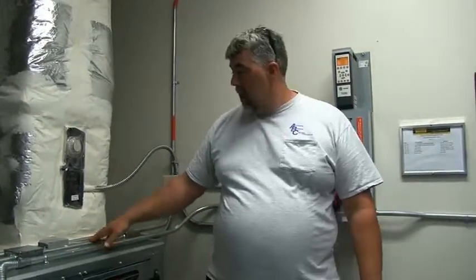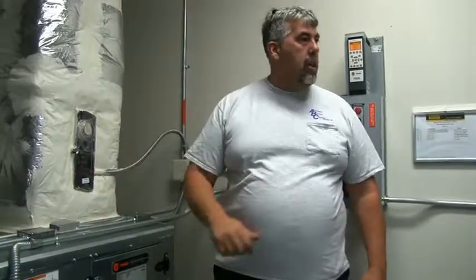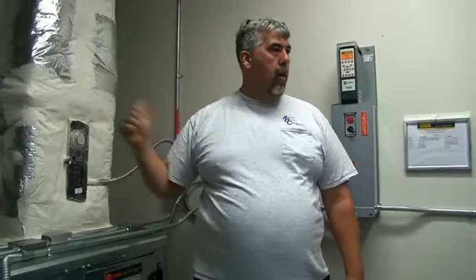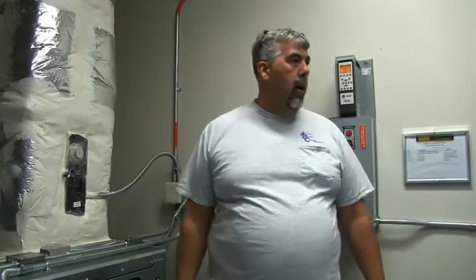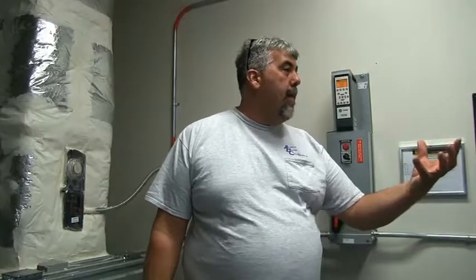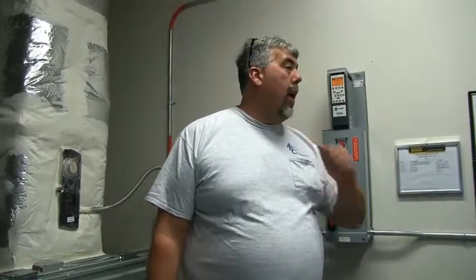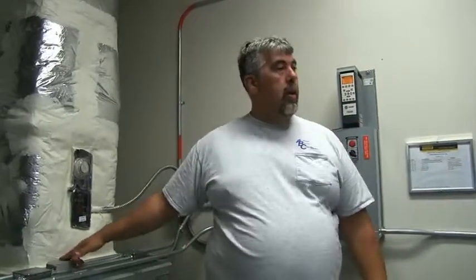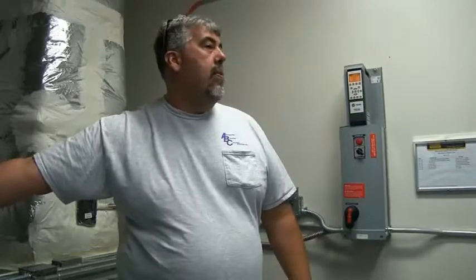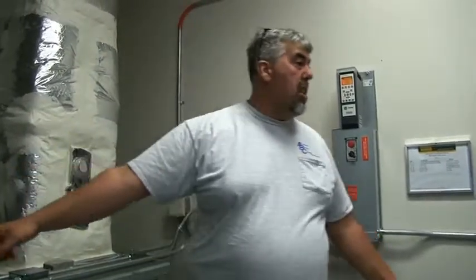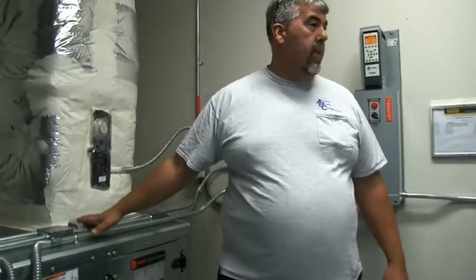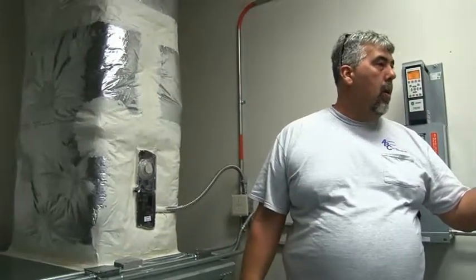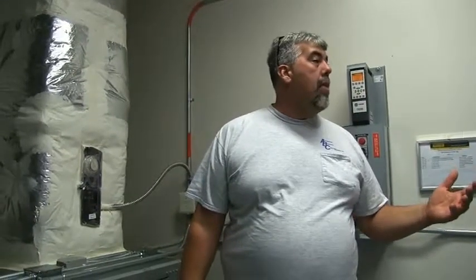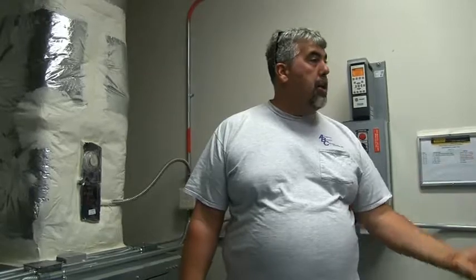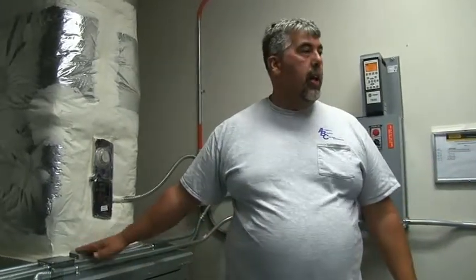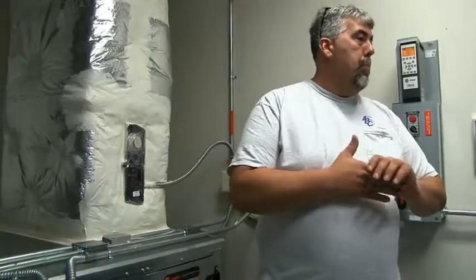And where's that mounted at? Is that the averaging sensor? It mounts here, but it goes in this way because it's like a cable. It runs in and they run it across the opening here. Okay, so it's like at the bottom of the opening like this. Right, and it's got 4 sensors in it that average the temperature. Okay. So, since you brought that up, if it ever fails, you'll know. Because you'll see this one saying it's 54 degrees, 55 degrees, whatever, close to its set point. And then you'll see this one saying 85. So one sensor went out and it's still using that 0, or it might fail the other way. I think it fails the other way. So we're using that 140 to average in with the other one saying 54. So now your temperature jumps up to 80 degrees, and you know it's not 80 degrees. That tells you the sensor's failed. Just for troubleshooting purposes on your end.